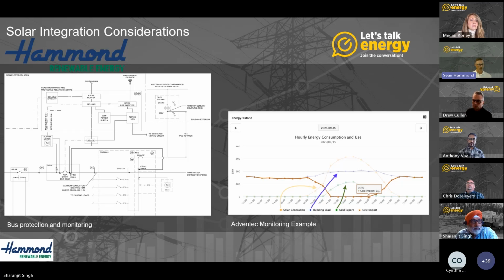These two images on the slide show, on the left, an example of how we're tying in and protecting switchgear, typically looking like this at an average light industrial manufacturer in Ontario—so how inexpensive is our connection cost. The best example of a cost-saving opportunity: if one facility has 208 volt infrastructure and another has 600 volt infrastructure, the 600 volt site is going to be way less expensive on the electrical and inverter side to connect solar.